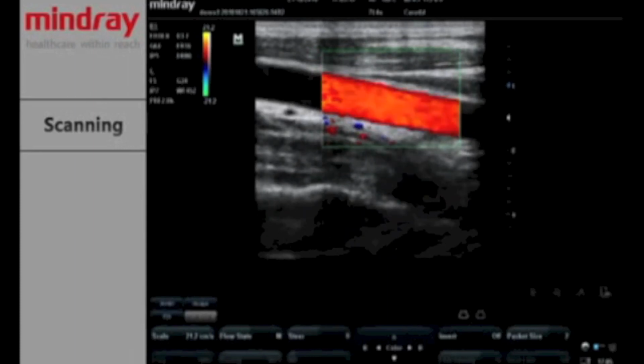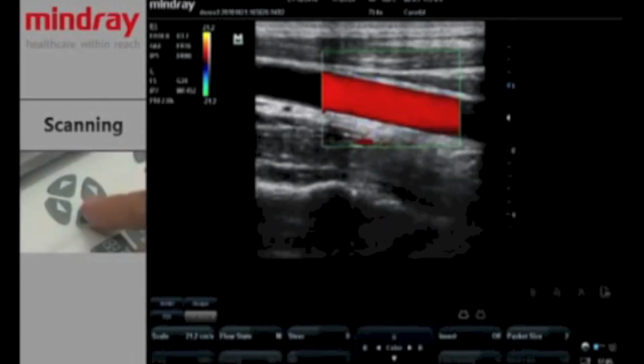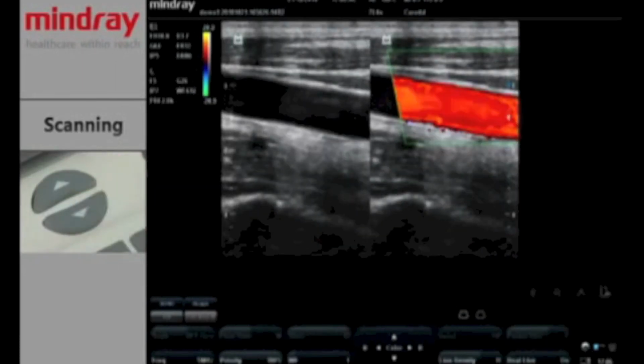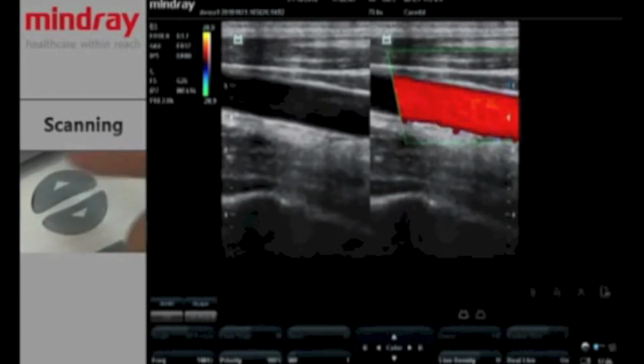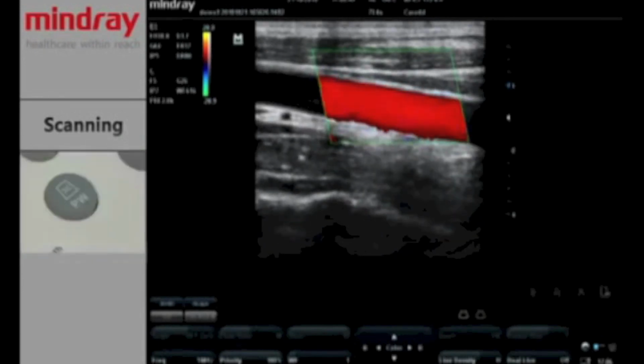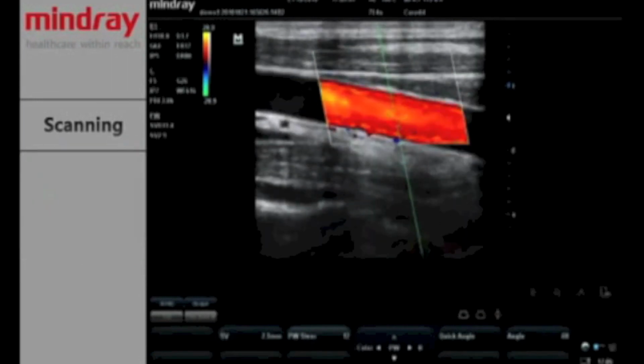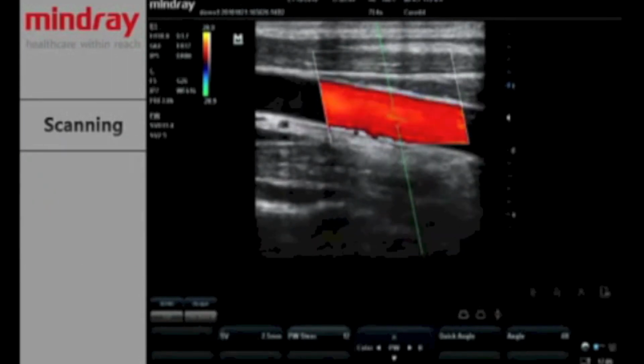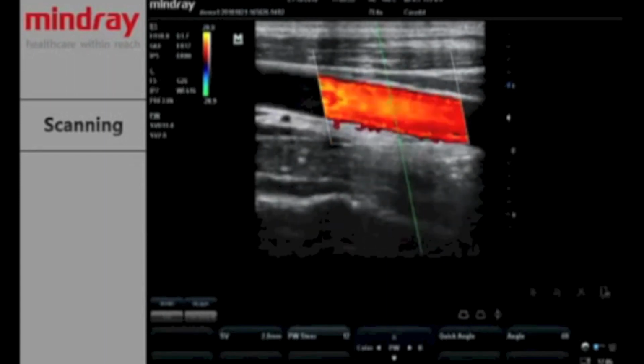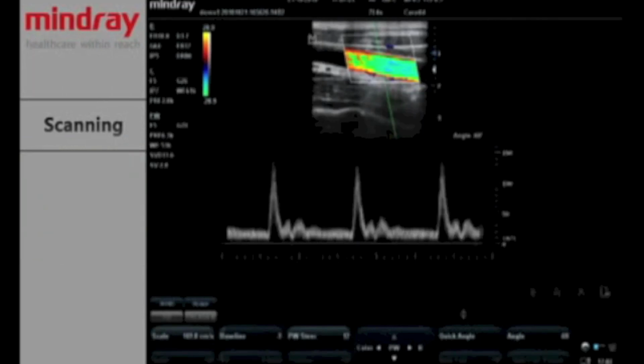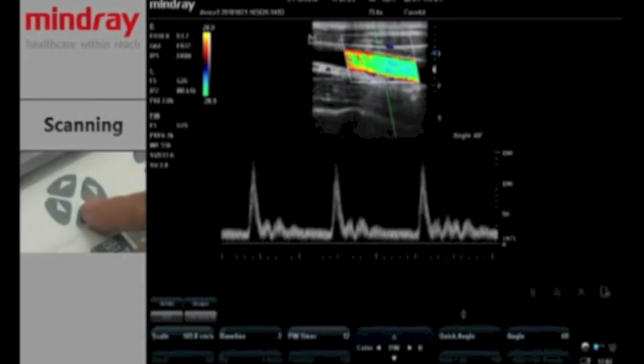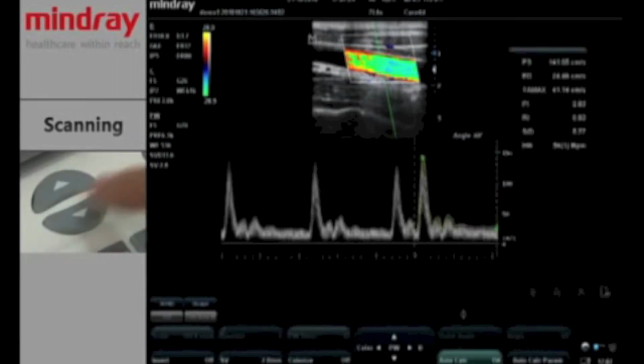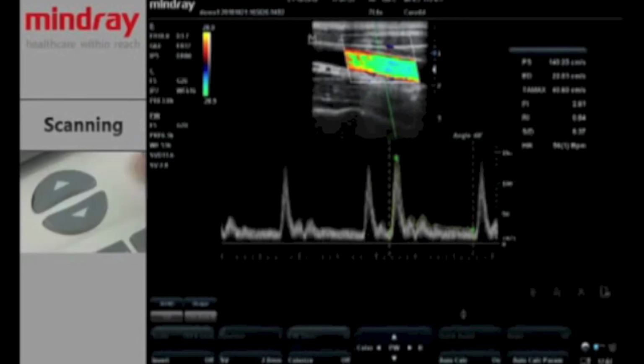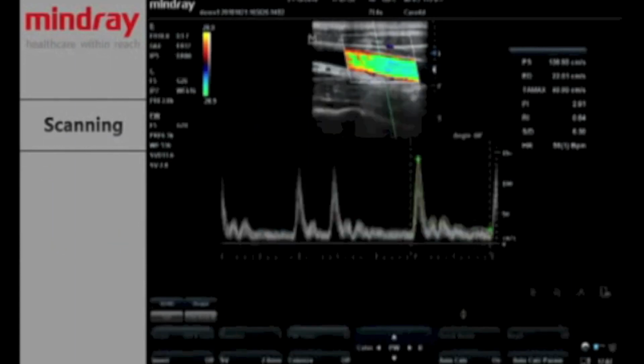We can realize the influence of the angle on the blood flow display. Turning on Duo Live, we can compare the color image with the 2D image live. Press the Power button and enter Power mode to display more vessels more sensitively. Enter the PW mode by pressing the PW button, and then choose a proper sample volume according to the size of the vessel by soft menu key. In the main vessel, sample volume should be half to two-thirds of the vessel width. In the branch vessel, sample volume should be half to full size of the vessel width.